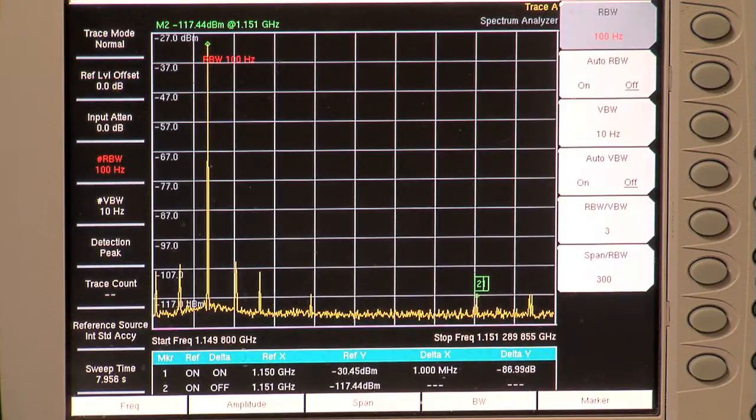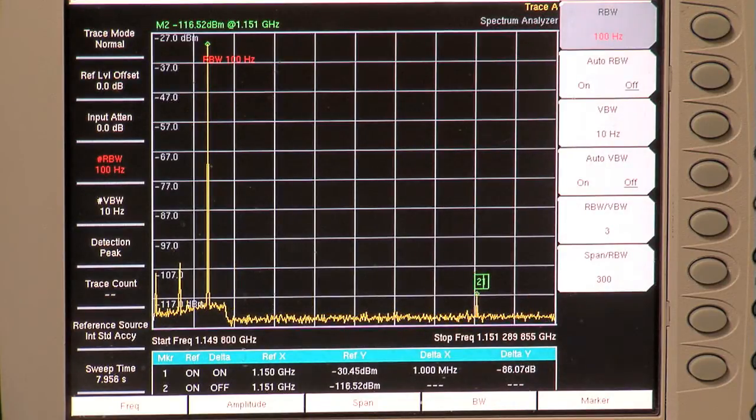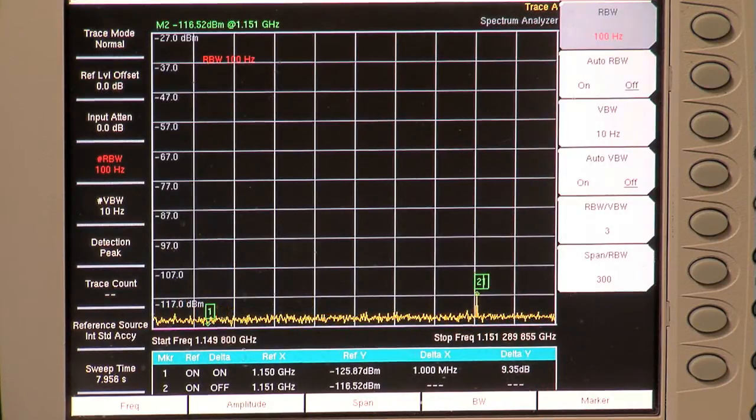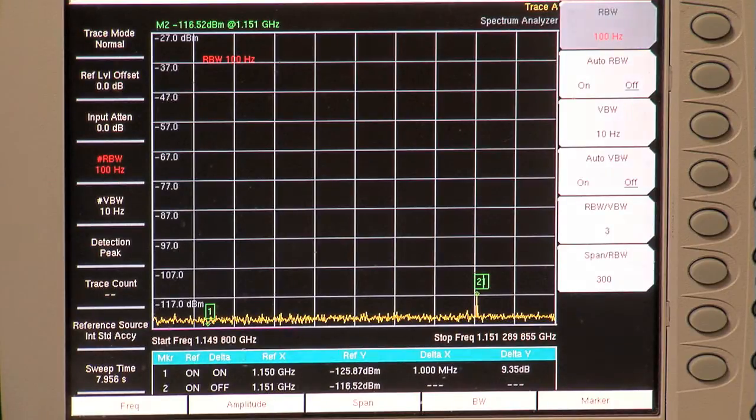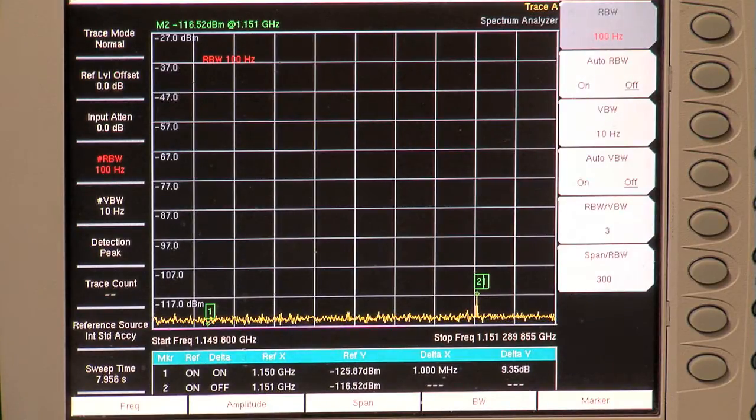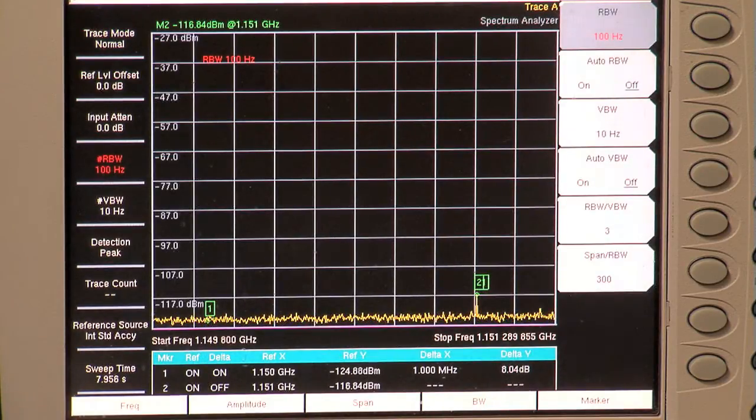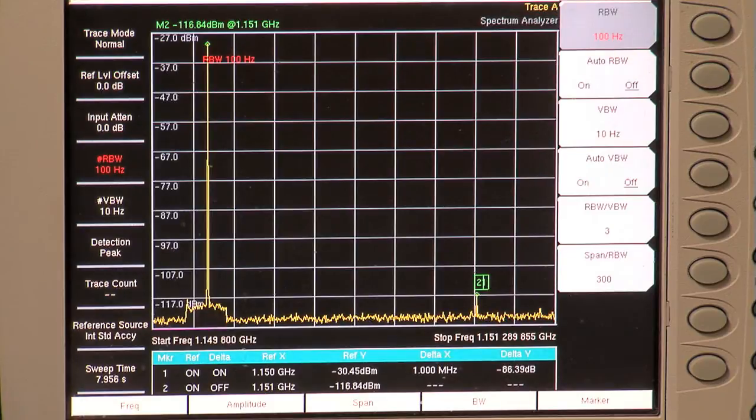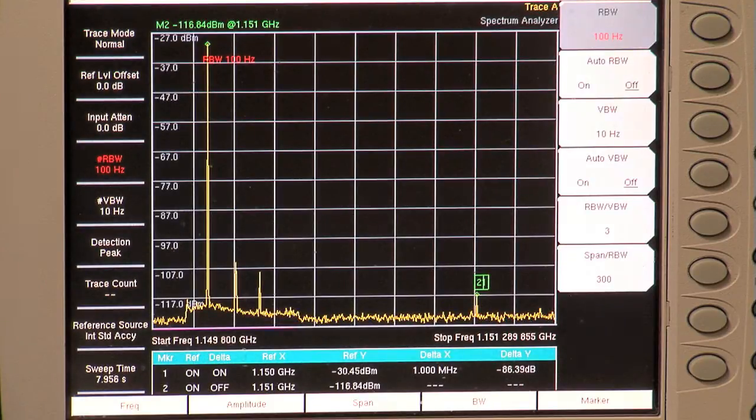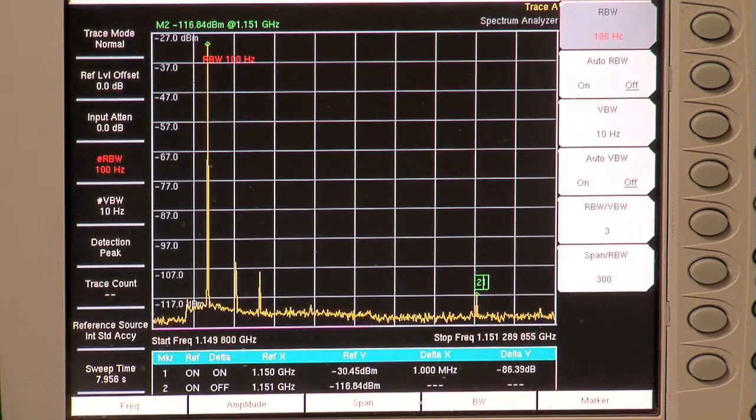Direct measurement is an excellent way to determine dynamic range. Start by measuring a very small signal by itself. This is easy to do with a marker. Then turn on a large signal and place a delta marker on the large signal. Use the marker table to see both values at once.